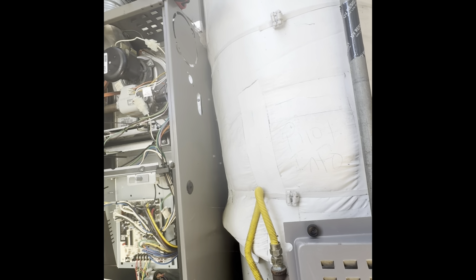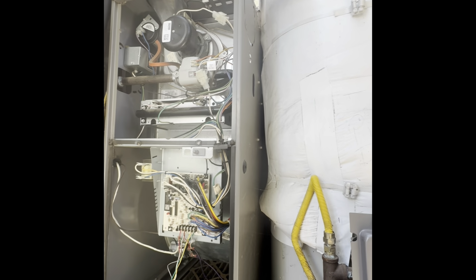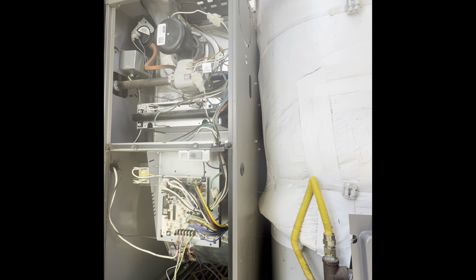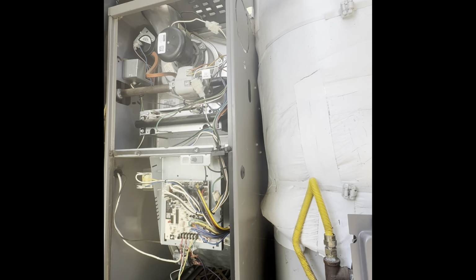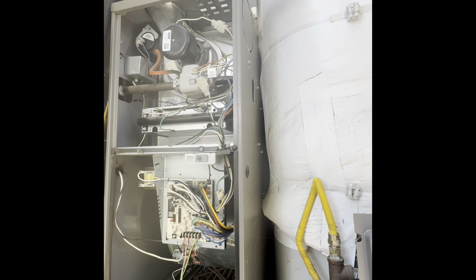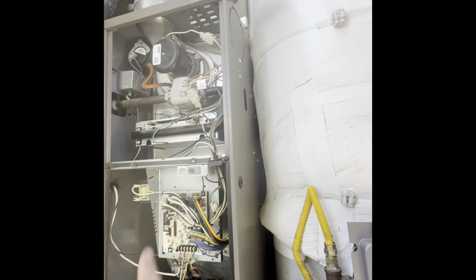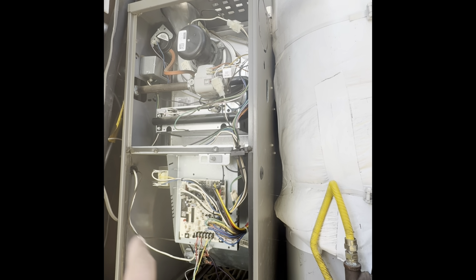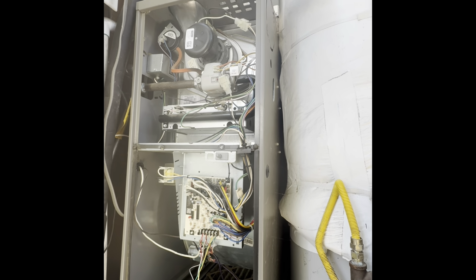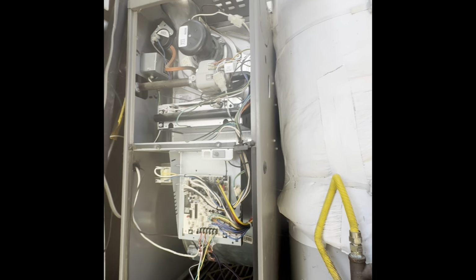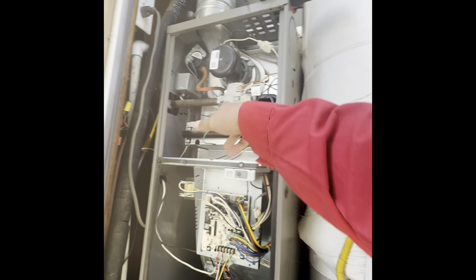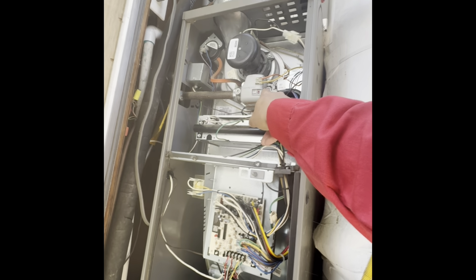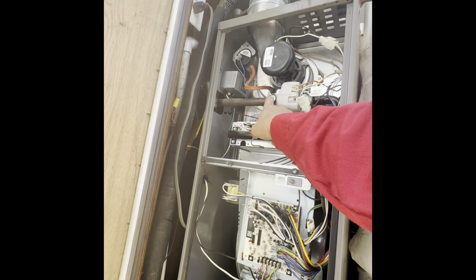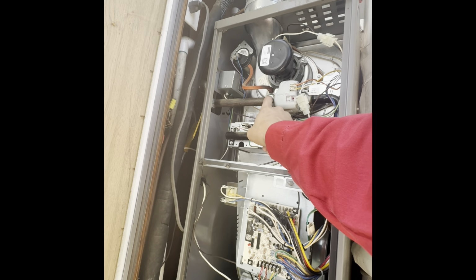So for now, unfortunately my camera died and I was not able to record that I checked the gas pressure and the static pressure of the system. Those are things that we have to check to make sure the system is working as efficiently as possible and doesn't create issues in the long run. I also recommended a blower cleaning. Blower cleaning is recommended due to lack of airflow and many other issues that can happen down the road. So, but yeah, I was getting about 3.41 here at the supply side, and I was getting about 7.32 over here in the inlet. The static pressure was a little low on this side.